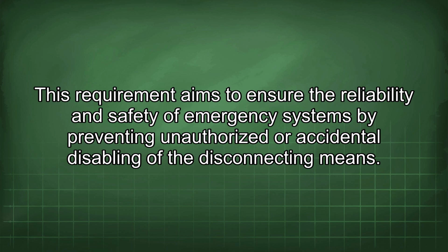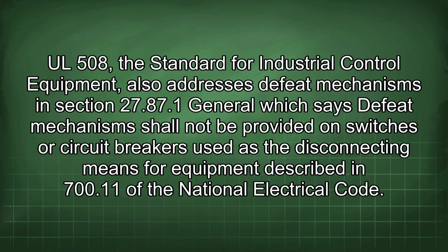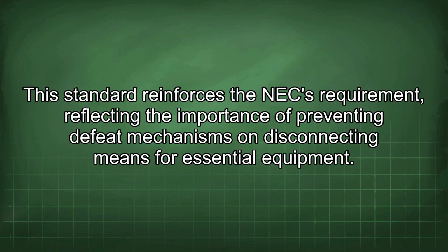disconnecting means. UL 508, the standard for industrial control equipment, also addresses defeat mechanisms in Section 27.87.1 General, which says defeat mechanisms shall not be provided on switches or circuit breakers used as the disconnecting means for equipment described in 700.11 of the National Electrical Code. This standard reinforces the NEC requirement, reflecting the importance of preventing defeat mechanisms on disconnecting means for essential equipment.